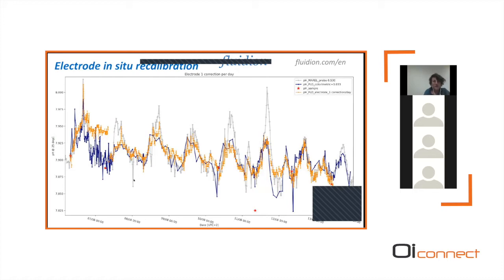That's been done here, and this is the first 24 hours, where you have quite an important drift on the sensor. After that, with this correction, once the electrode has equilibrated with the seawater, it follows really nicely the colorimetric analyzer data, despite doing only a single point correction per day. Interestingly, you also obtain the same amplitude of the diurnal pattern, whereas the multi-parameter probe originally installed shows a much larger diurnal pattern. And here I'm not entirely sure what we're observing.